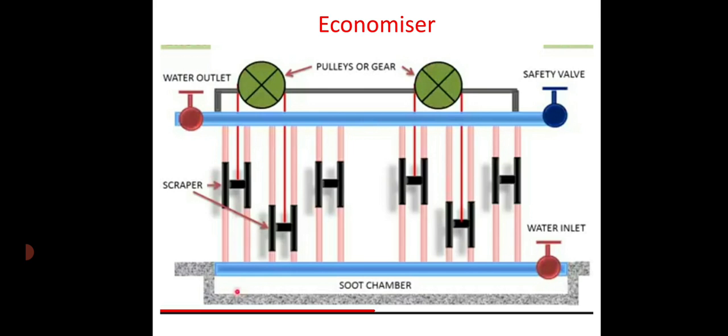It is essential that the vertical tubes be kept free from deposits of soot, which greatly reduce the efficiency of the economizer. Each tube is provided with a scraper for this purpose. The scrapers of two adjacent sections of tubes are grouped together and then coupled by rods and chains. If the temperature of the feed is less than 35 degrees centigrade, then there is a danger of corrosion due to the moisture in the flue gases being deposited on the cold tubes.